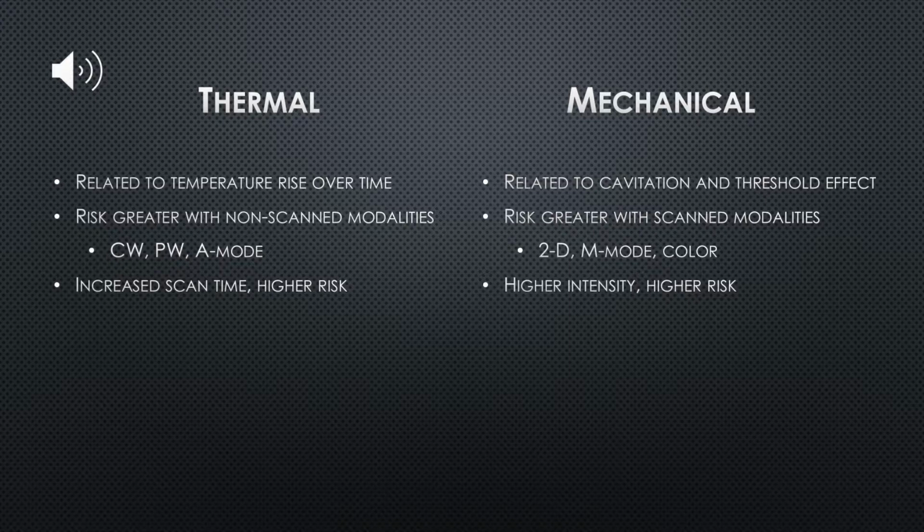So some of the basic differences with the bioeffects. With thermal, they are related to a temperature rise over time, and the risk is greater with non-scanned modalities, such as continuous wave, pulse wave, and A mode, because they have a longer listening time. With thermal, an increased scan time gives you a higher risk of bioeffects.